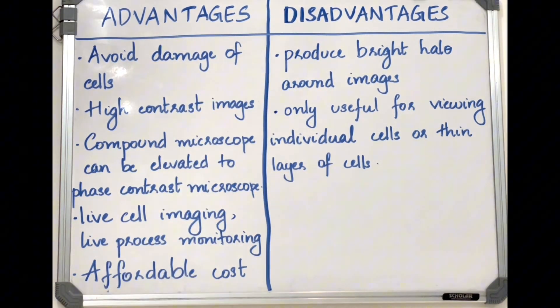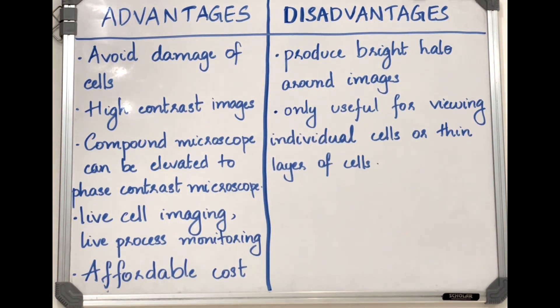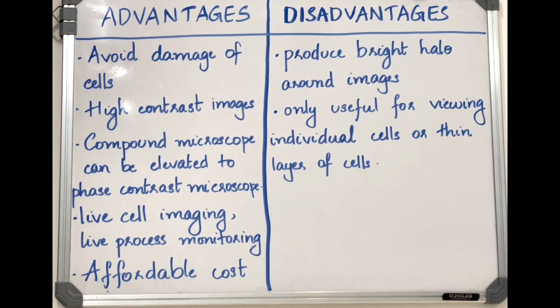The disadvantage is that the phase contrast microscope produces a bright halo around images. This is because of incomplete separation of the direct unretarded rays and the deviated retarded rays. Another disadvantage is that it is only useful for viewing individual cells or thin layers of cells.